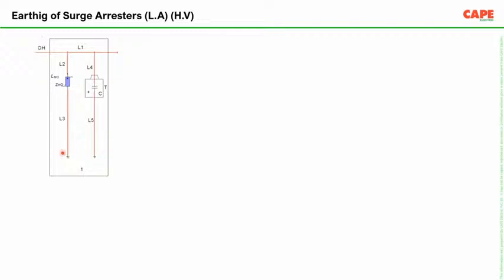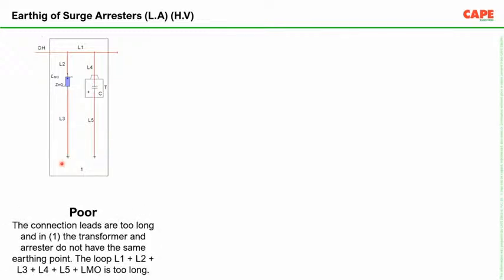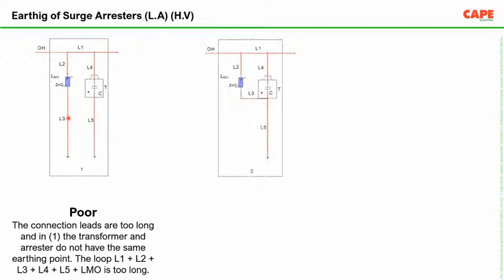Maybe the earth pit, everything is interconnected together. This is one way of installation. Basically, this is a poor quality installation, because of the lead length. Once the lightning current flows through this wire length, a lot of voltage drop happens in it. As a result, the stress which goes into your transformer is very high. So this is actually not the recommended way.